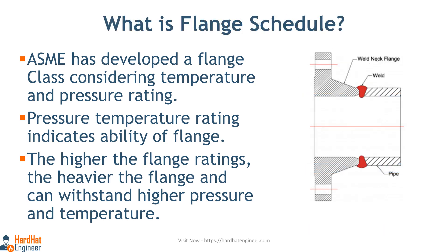Now let's move on to flange schedule, which is related to pipe thickness. As you know, flanges are welded with piping components. So for flanges, we have to specify two dimensions: the first is the flange class and the second is the flange schedule. Flange schedule refers to the thickness of the flange neck which will be welded with a pipe. It helps in determining the compatibility between pipes and flanges to avoid mismatch of internal diameter, and is primarily used for pipe sizing.